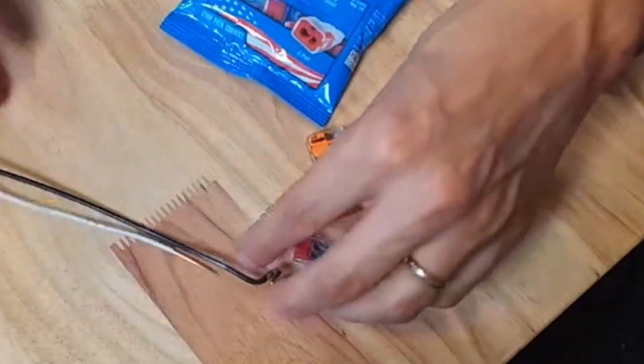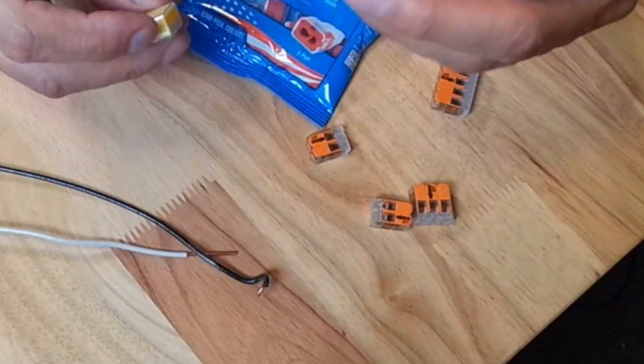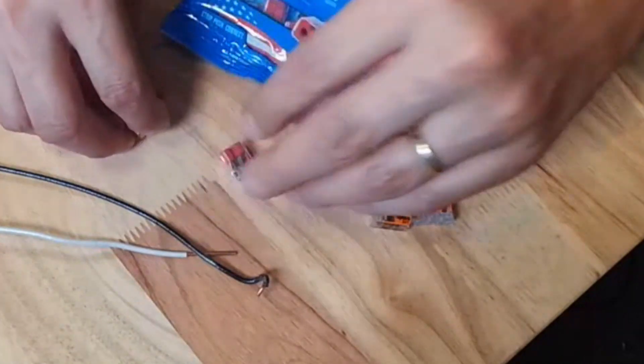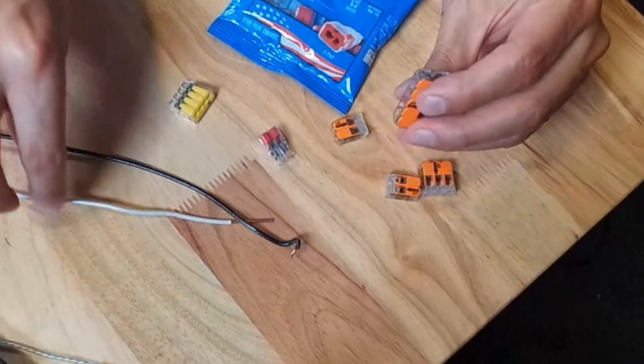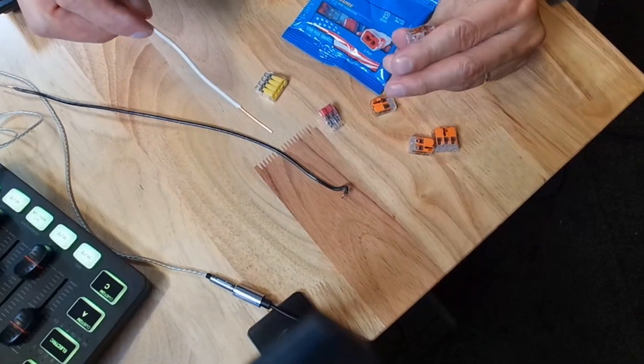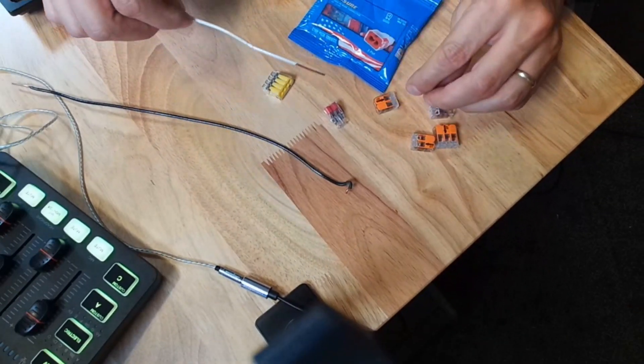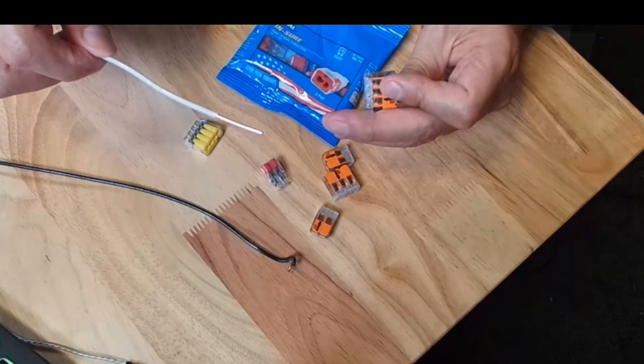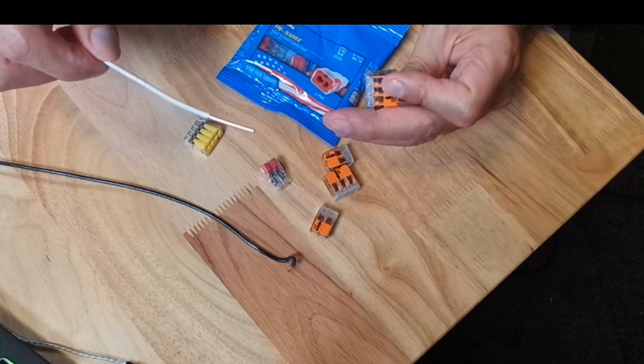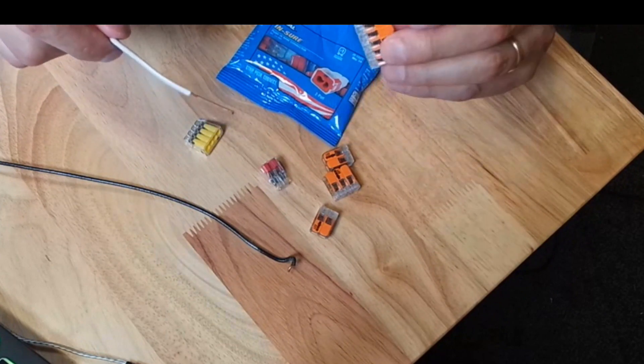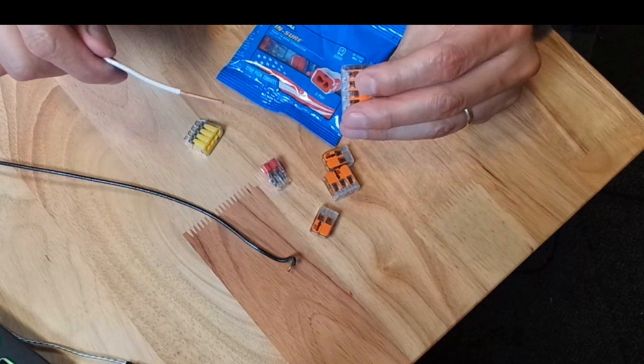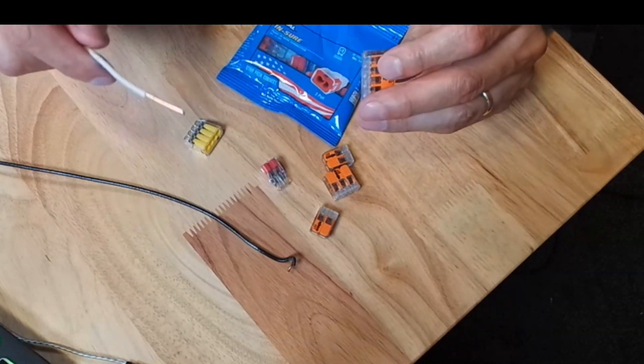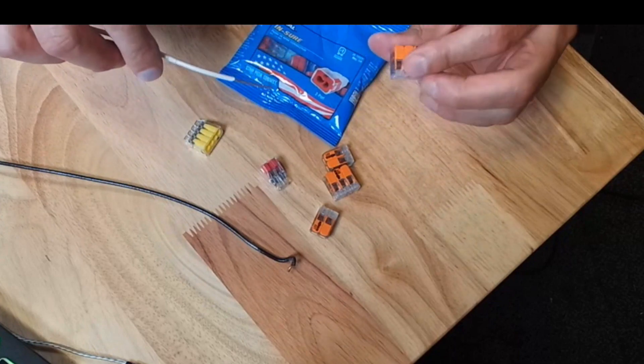The Ideal line comes in two to four sizes. Both brands are rated for similar wire sizes. The Ideal is rated for 20 gauge to 12 gauge wiring. The Wago connectors are size 24, which is tiny wire, to size 12. They're very similar, basically 12 to 20 gauge wire.